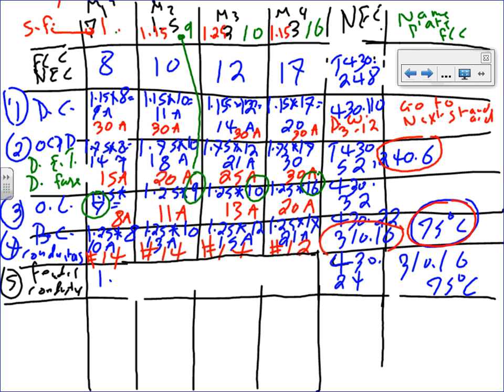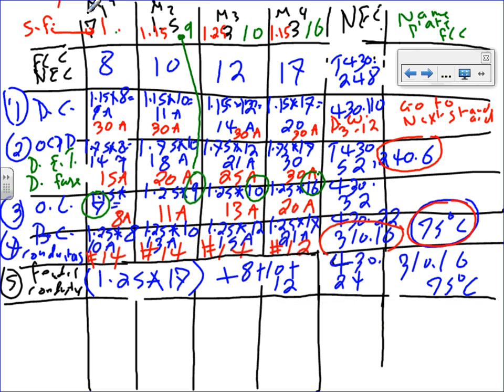17. 1.25 times the largest motor amp 17, but in between brackets, plus all the full load current of all the other motors. What are the other motors? 8 plus 10 plus 12. Now, would I add the 17 again? Would I add the 17 here? 17 is already used there. So you bump the largest motor 25% extra, and you add the full load current of all the others.